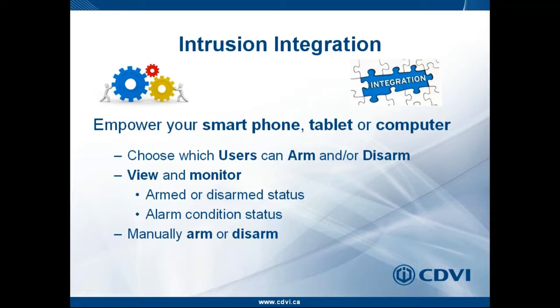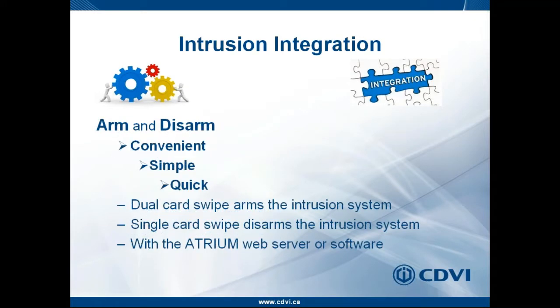Once integration is complete, you will be able to see if the system is armed or disarmed and whether the building is in alarm. You can manually arm and disarm through a button on the web interface or PC software. For card-based control, you double-swipe your card — swiping the same card twice at the reader within five seconds — to arm the alarm system. A single card swipe will disarm the alarm system if you have disarming rights.